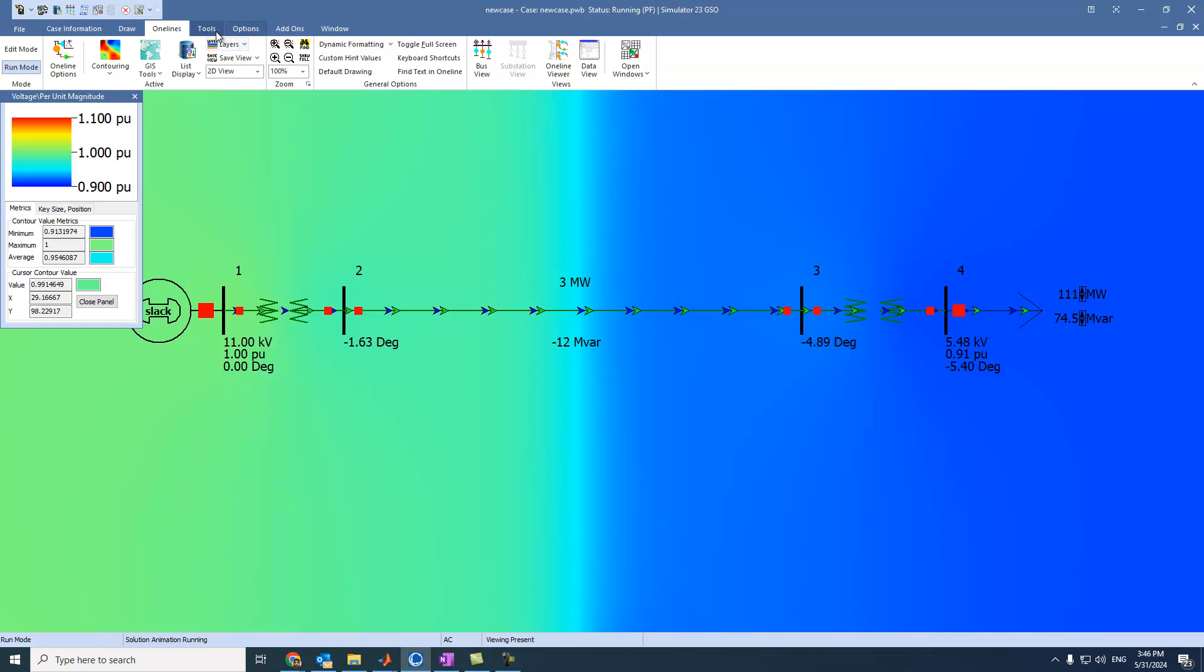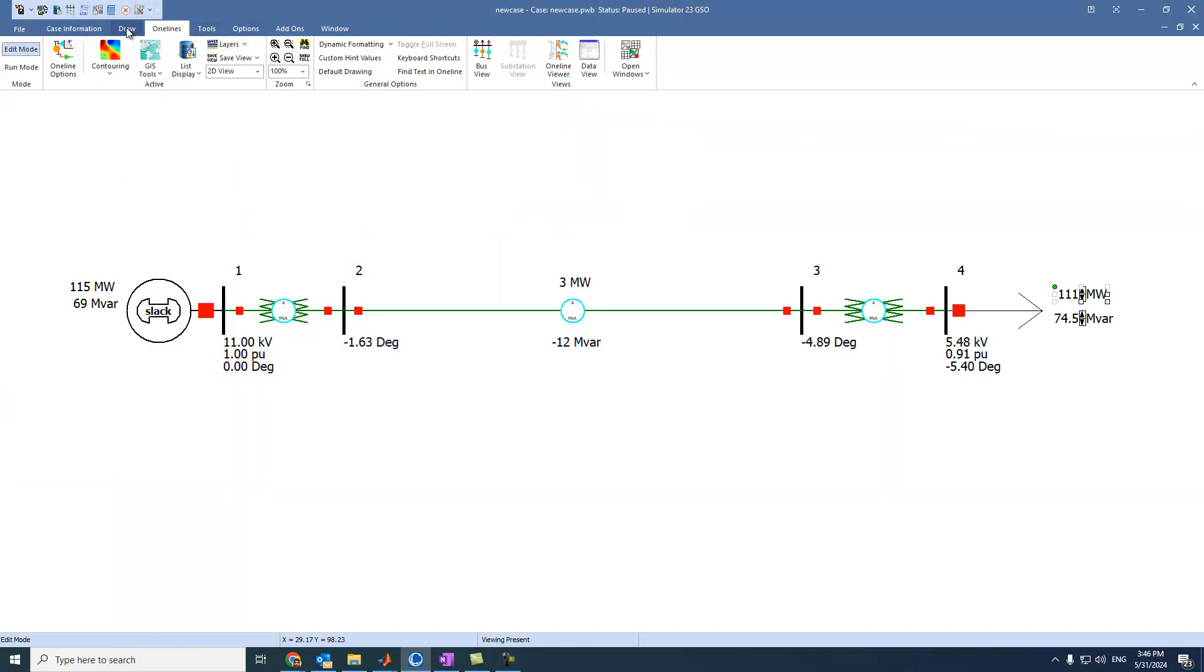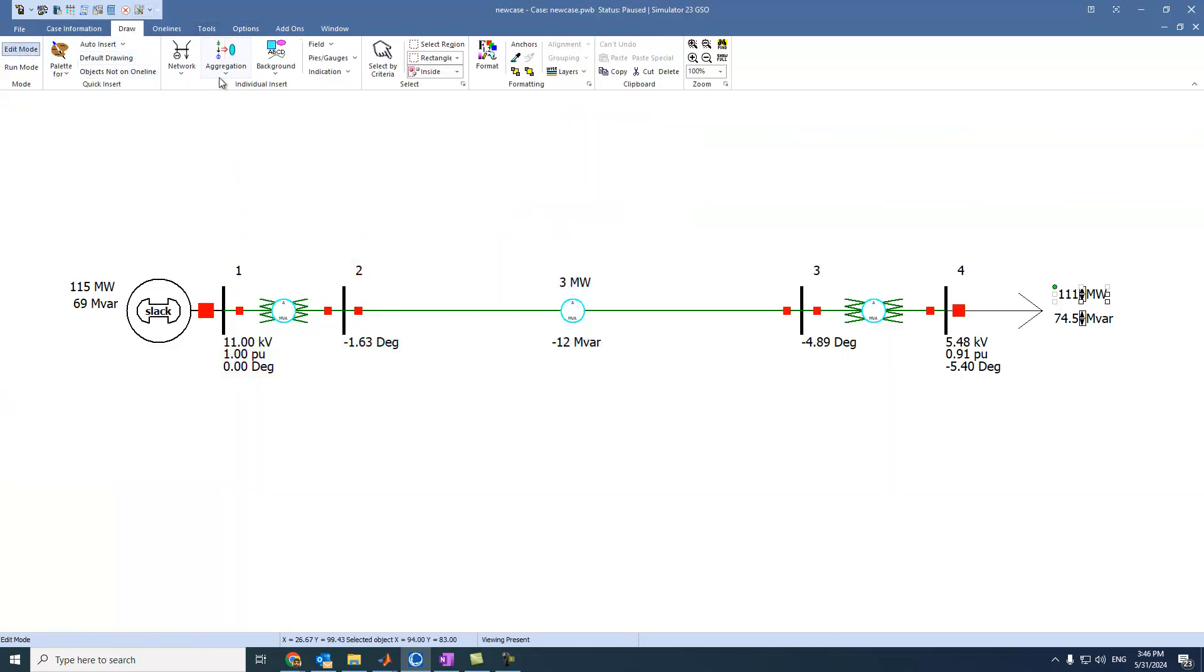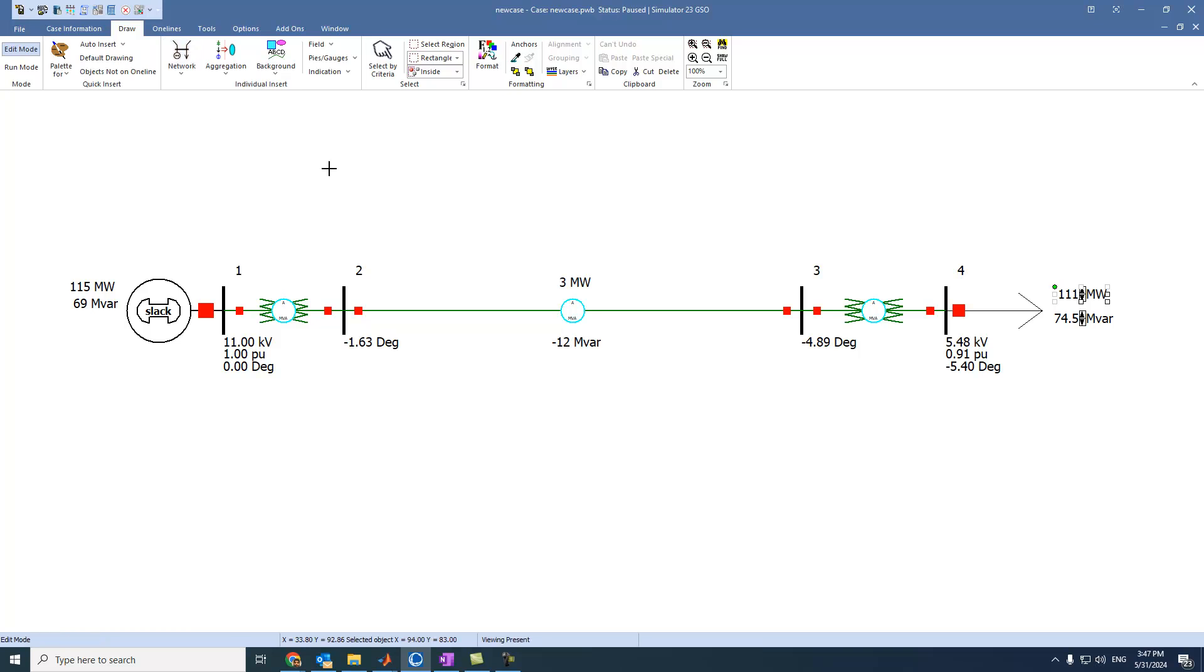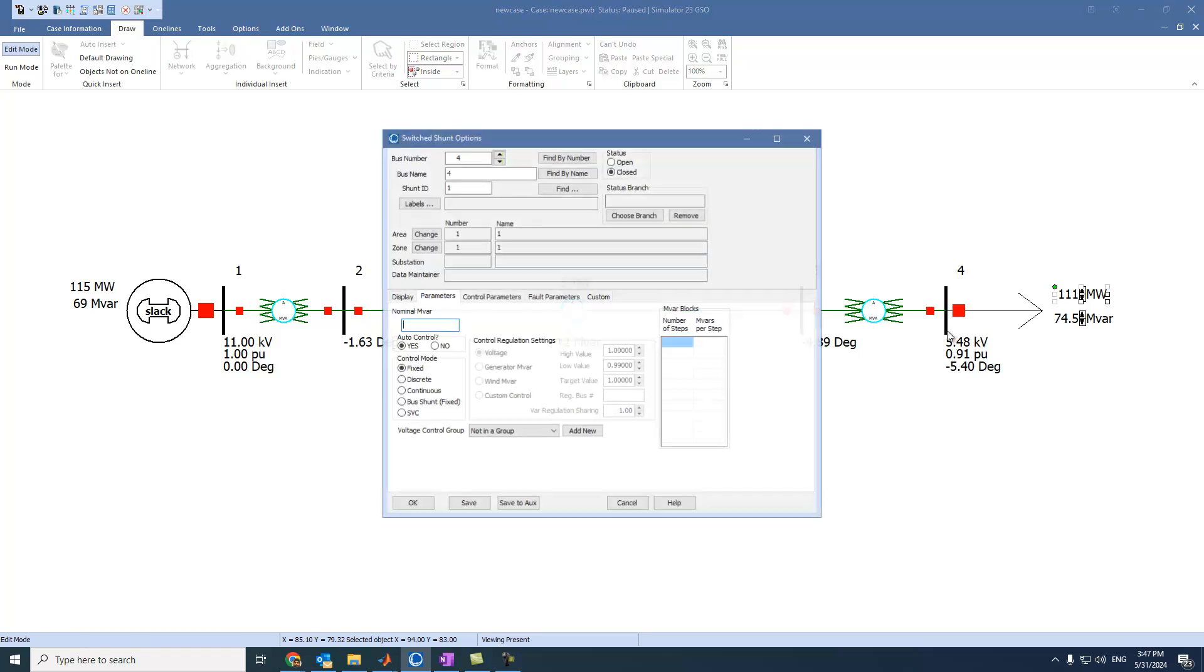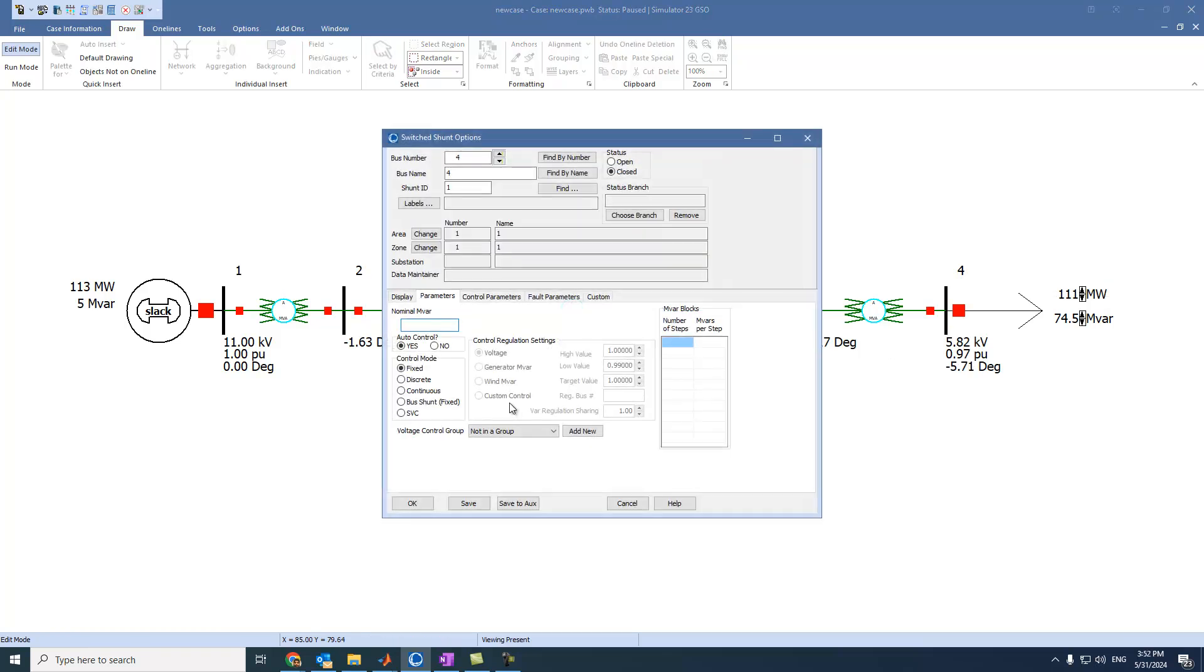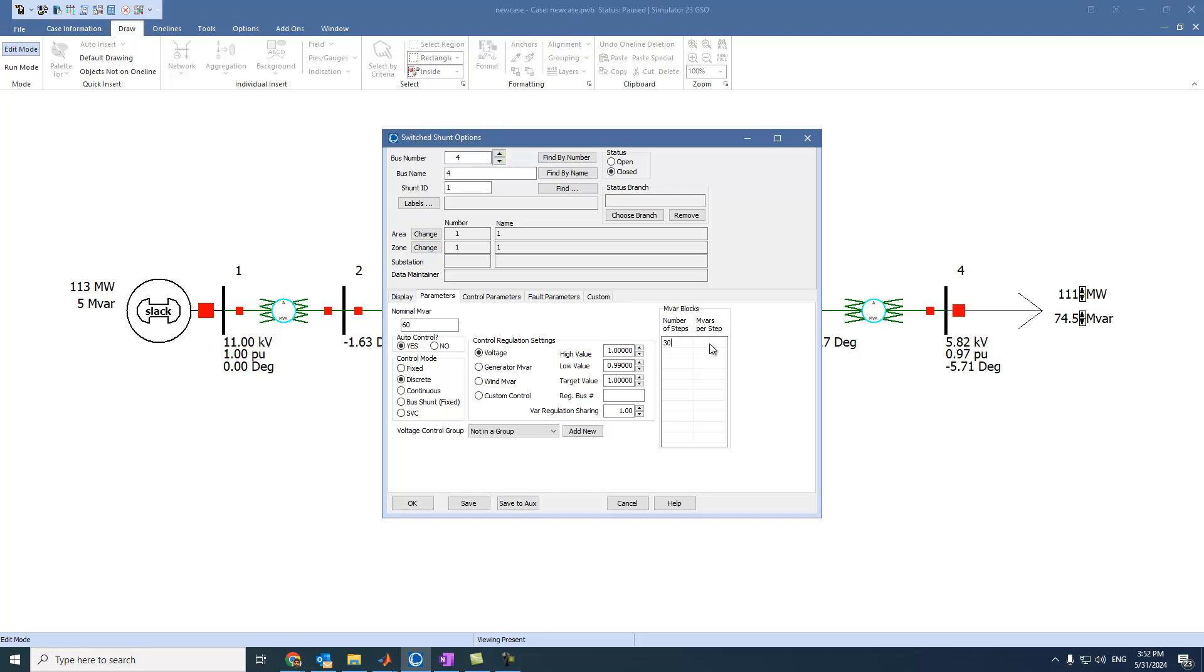So let's come here to edit mode and go to draw. And from the network, select a shunt or switched shunt and click on bus 4. Let's say it is around, for example, we have 60 as nominal, just nominal. And let's select here, it is discrete. And it is moving with, for example, 30 steps. And megavar per step is 2.